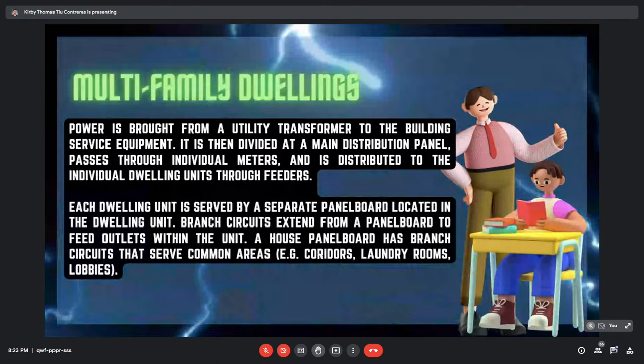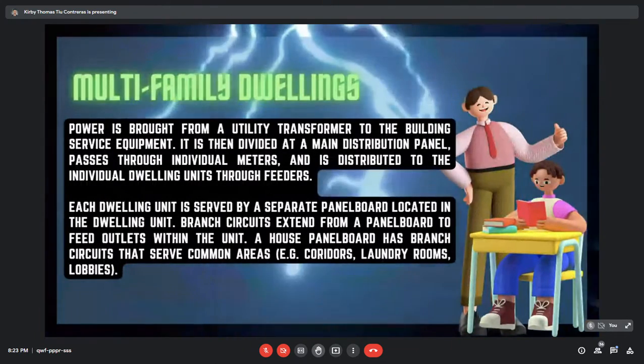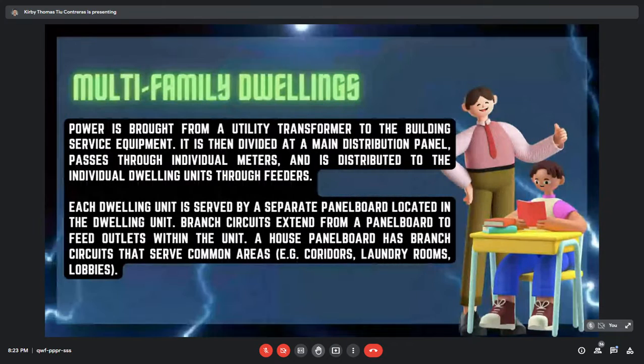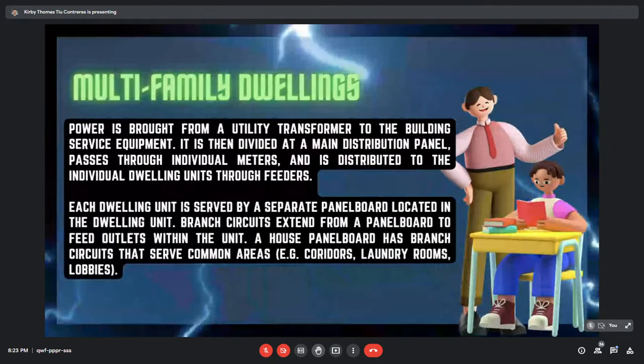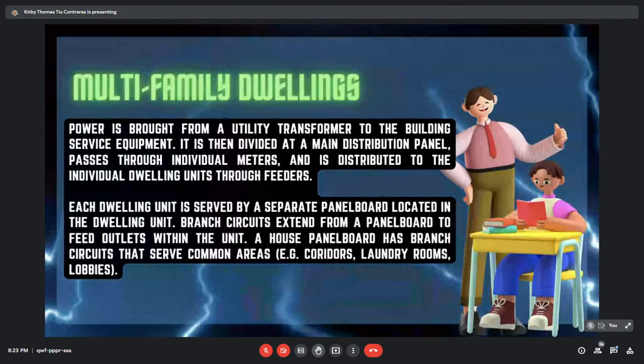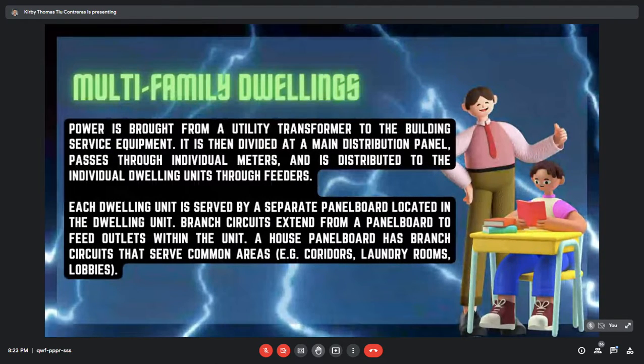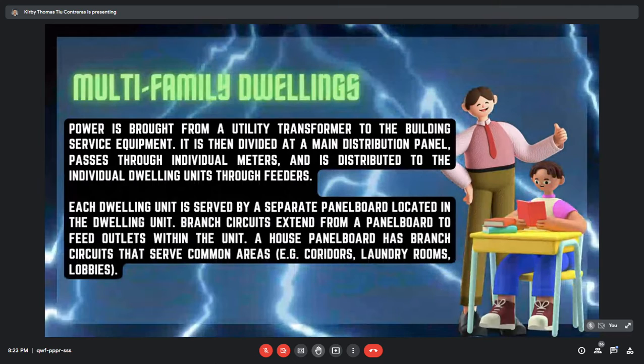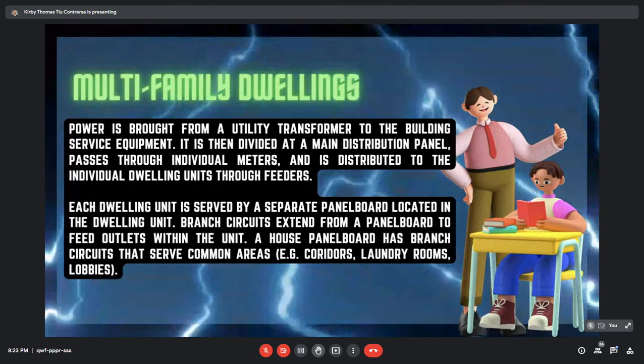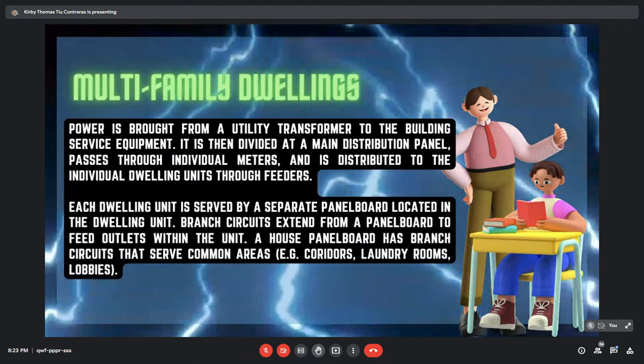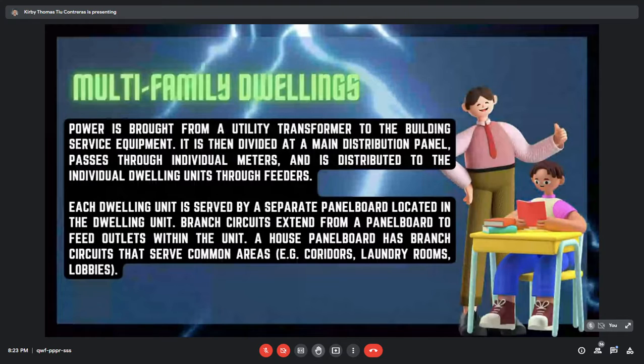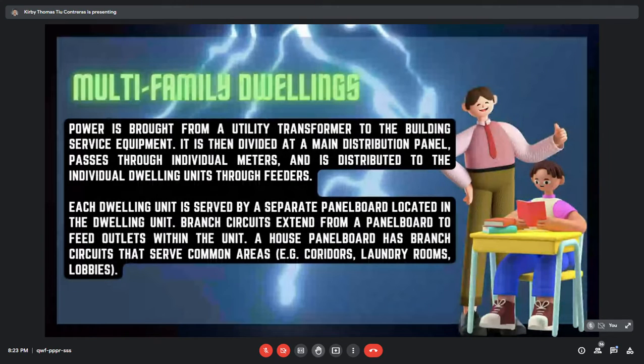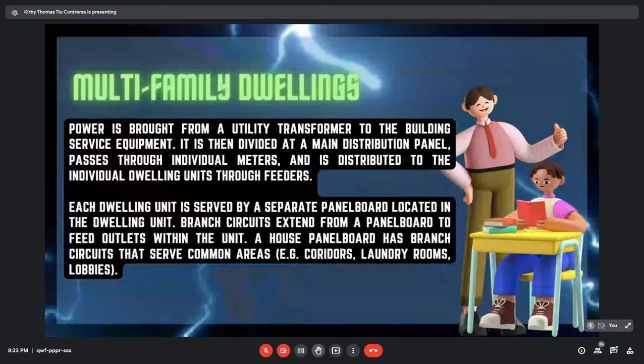In multi-family dwelling units, power is brought from a utility transformer to the building service equipment. It is then divided at the main distribution panel, passes through individual meters, and is distributed to the individual dwelling units through feeders. Each dwelling unit is served by a separate panel board located in the dwelling unit. Branch circuits extend from a panel board to feed outlets within the unit. A house panel board has branch circuits that serve common areas like corridors, laundry rooms, and lobbies.